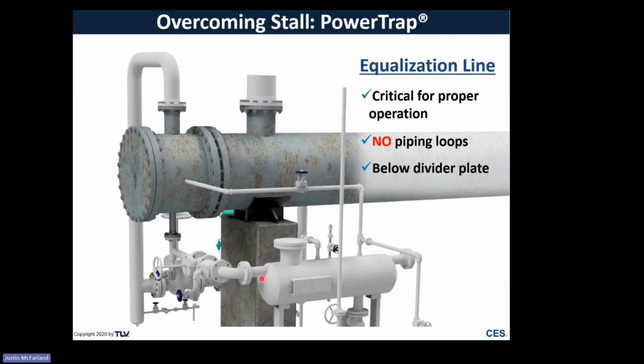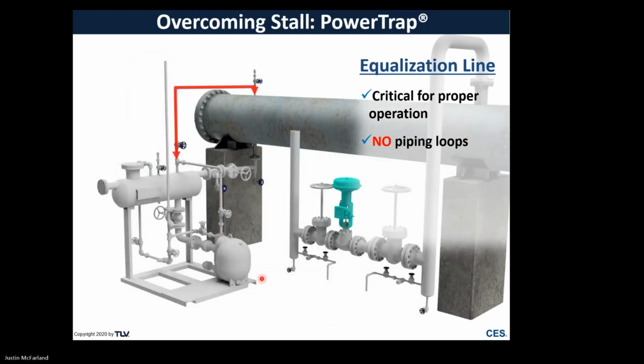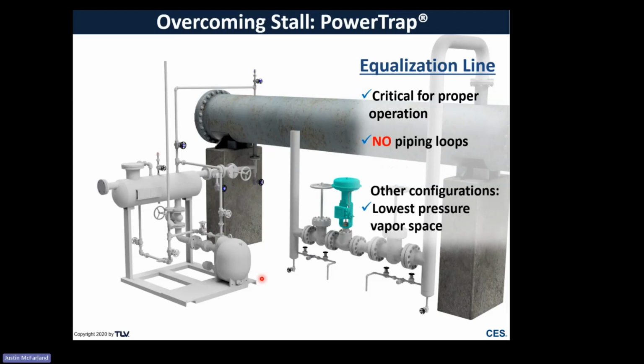So critical point here is that at least for shell and tube heaters, there's a specific location we want to make sure we're balancing to. It's a little easier when you've got a shell and tube heater with steam on the shell side. But the point that I'm really wanting to make is that TLV, if you ever are interested in utilizing a power trap system, or you're out in the field and you see another type of mechanical pump system, just understand that it requires balancing, and the balance point on the heater, whether it's a shell and tube, plate and frame, fin tube, or anything else, it needs to be balanced to the lowest pressure vapor space. And sometimes that might actually be the condensate outlet piping. And if so, it's just a lot of considerations for designing this piece of equipment and what those elevations and the sizing of various things look like.